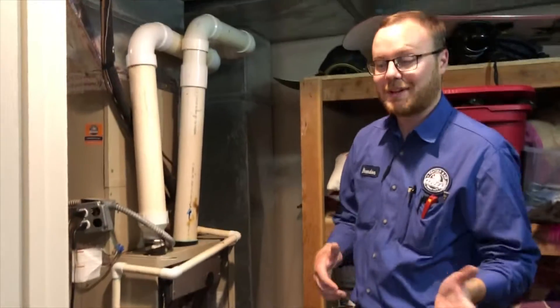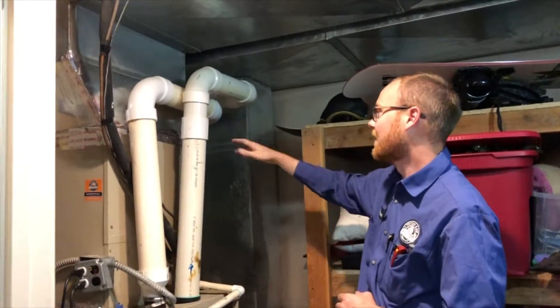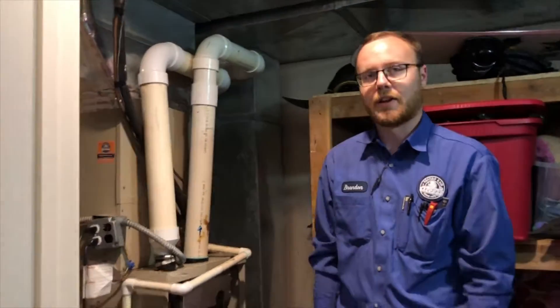There were a few things that made me want to look further into the condition of the heat exchanger. Those things include the fittings and the way the venting is run — if you look back here, it's taped together. Also, the amount of rust in the furnace itself can show that combustion gases are leaking. On this side, there's a lot more rust from where liquid from the furnace was dripping onto the ductwork. And just the condition and age of the system — it hasn't been serviced regularly and is over 10 years old, so there's a high likelihood things have started to wear down.